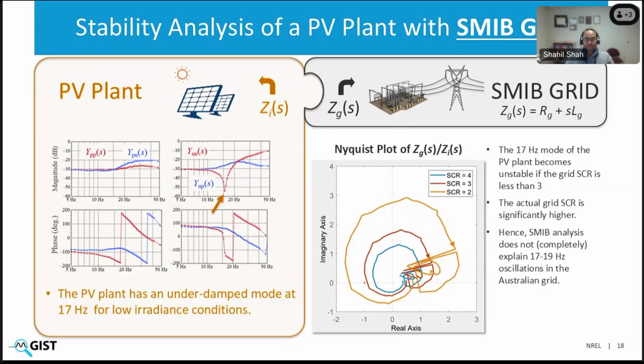So let me demonstrate steps 2 and 3. Nilesh already talked about step 1, so I'll talk about steps 2 and 3 very quickly. This is the stability analysis of a PV plant in a single machine infinite bus format. On the left, I'm showing the impedance response of a particular PV plant. And then we did that impedance scan for different operating conditions.